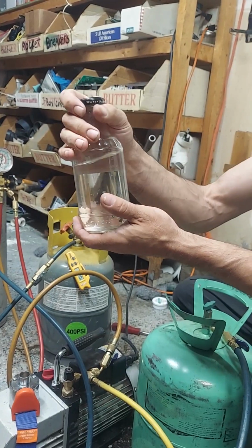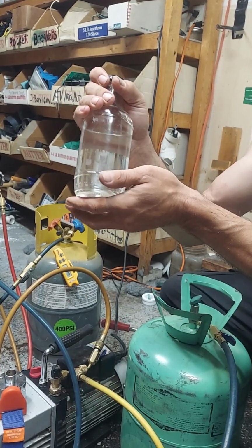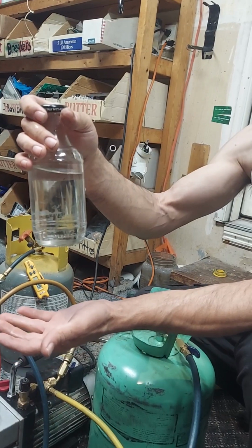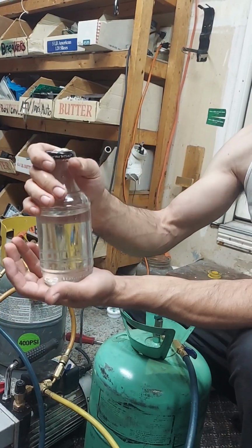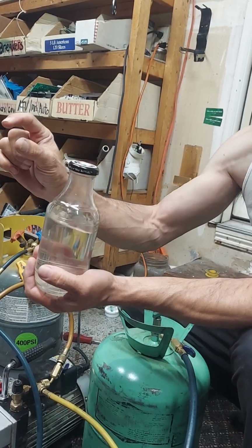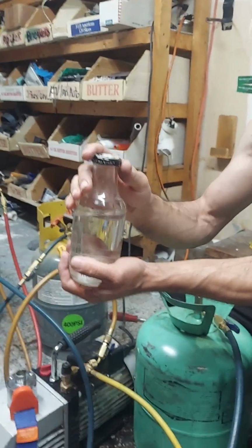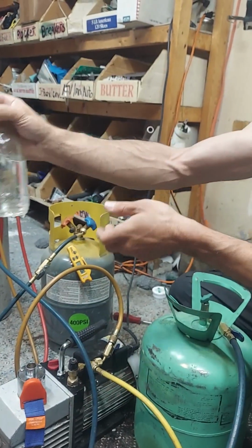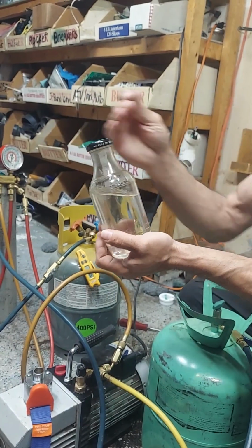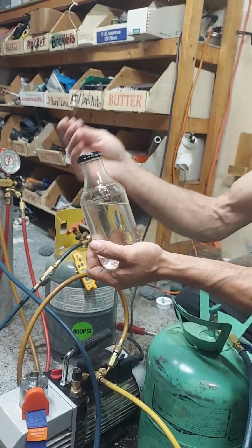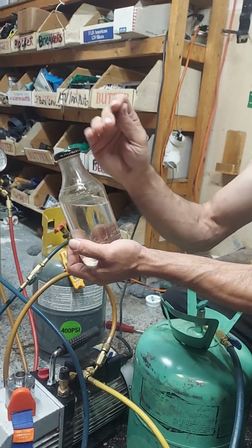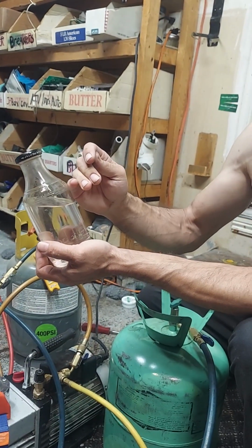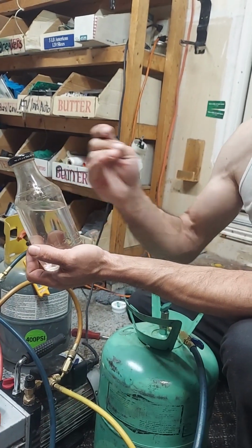So 1 BTU is, I'm sorry, 1 BTU is the amount of heat it takes to heat 1 pound of water 1 degree. That's kind of their calculation, just like 1 inch is 1 inch. It's just a standard measurement. So if I were to take this at 35 degrees, put it in the freezer, it'll go down to 34, remove a BTU. 33, remove a BTU. It'll go down to 32, remove a BTU. Now, it won't go to 31 by removing 1 BTU. I'm going to have to remove maybe hundreds of BTUs to change the state.